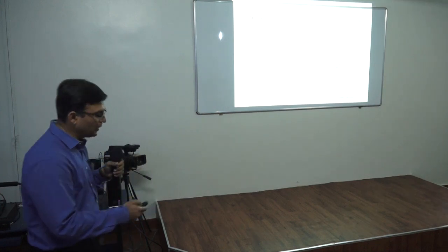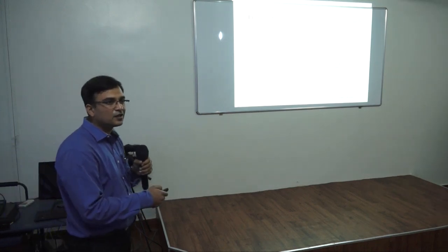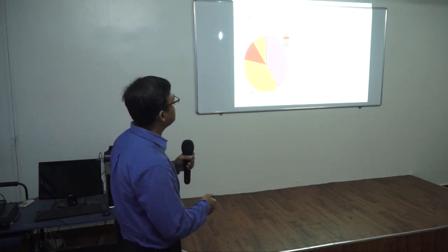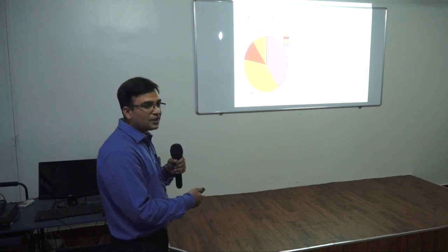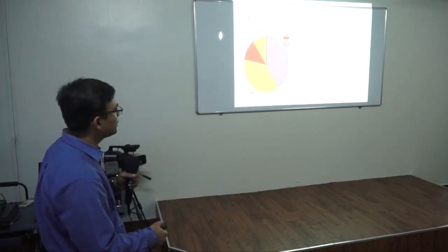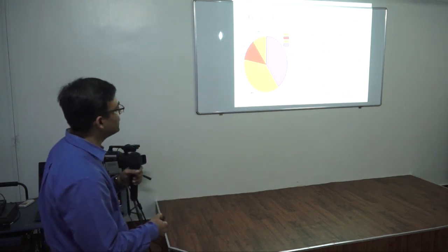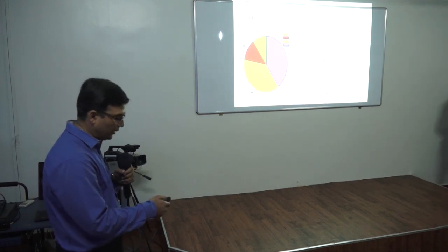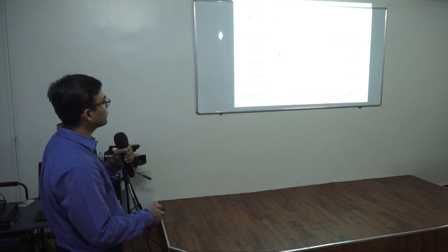So, if we go through the statistics, further focus should be that the one fault which is on the higher side should be selected. If we go through our induction motor fault statistics, we find that the bearing fault is maximum, and that is 40%. So my focus will typically be on the bearing faults in the induction motor.